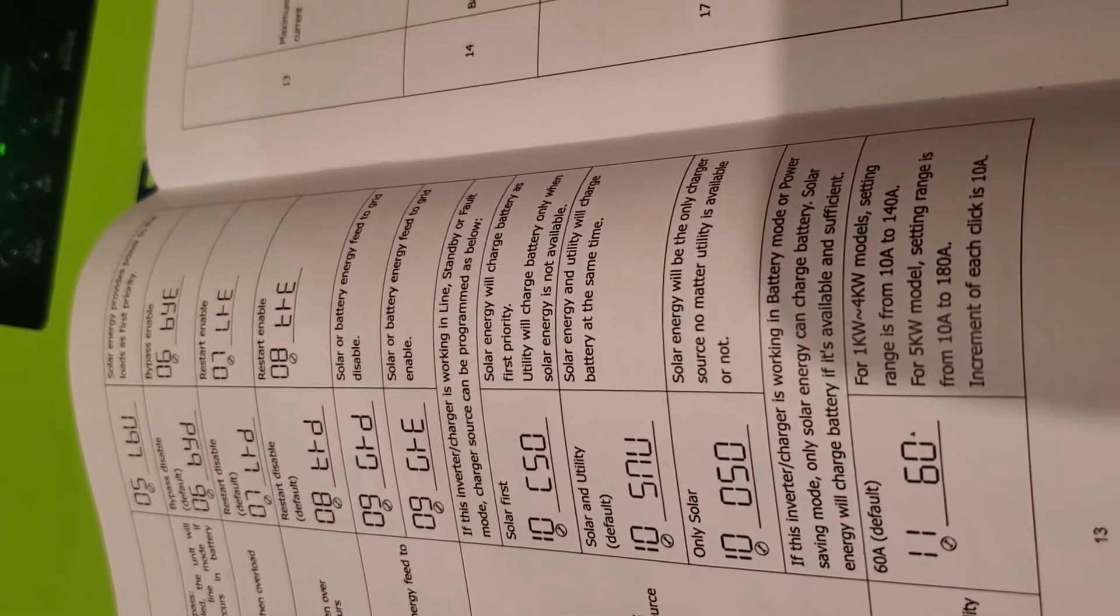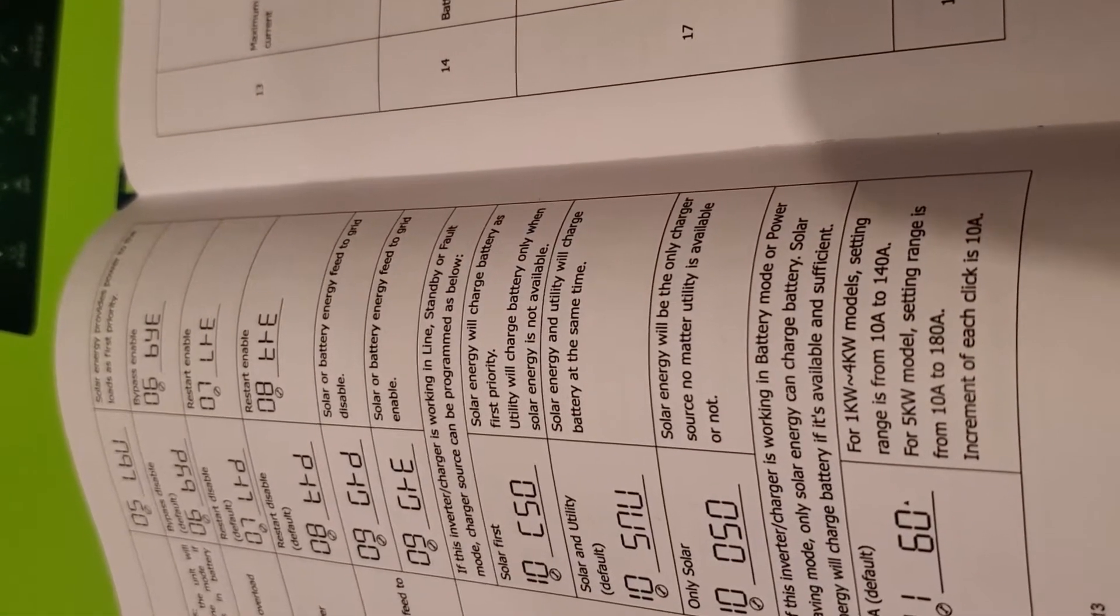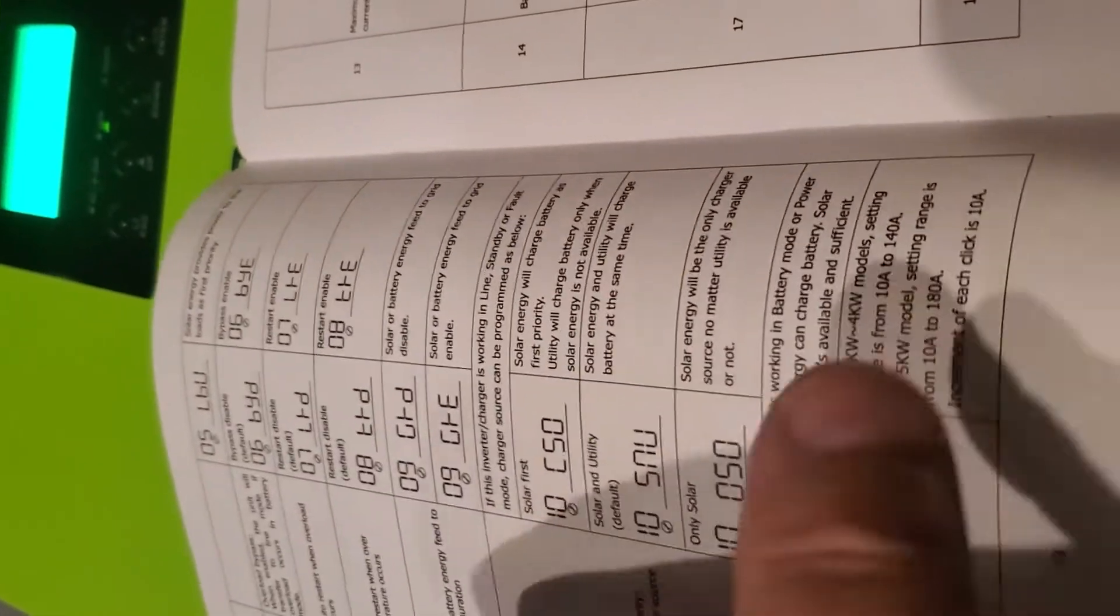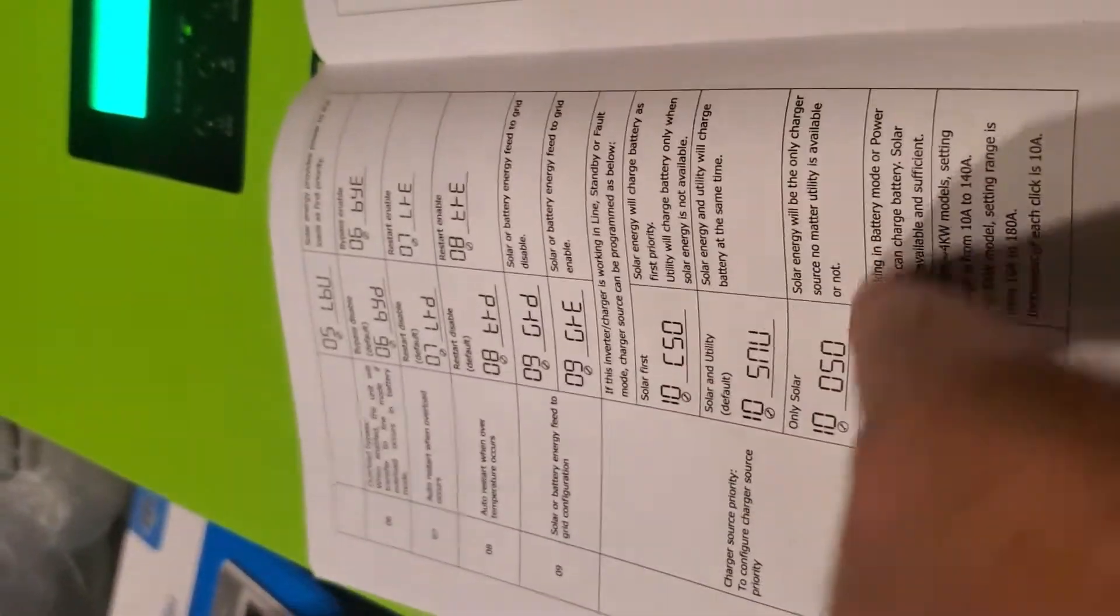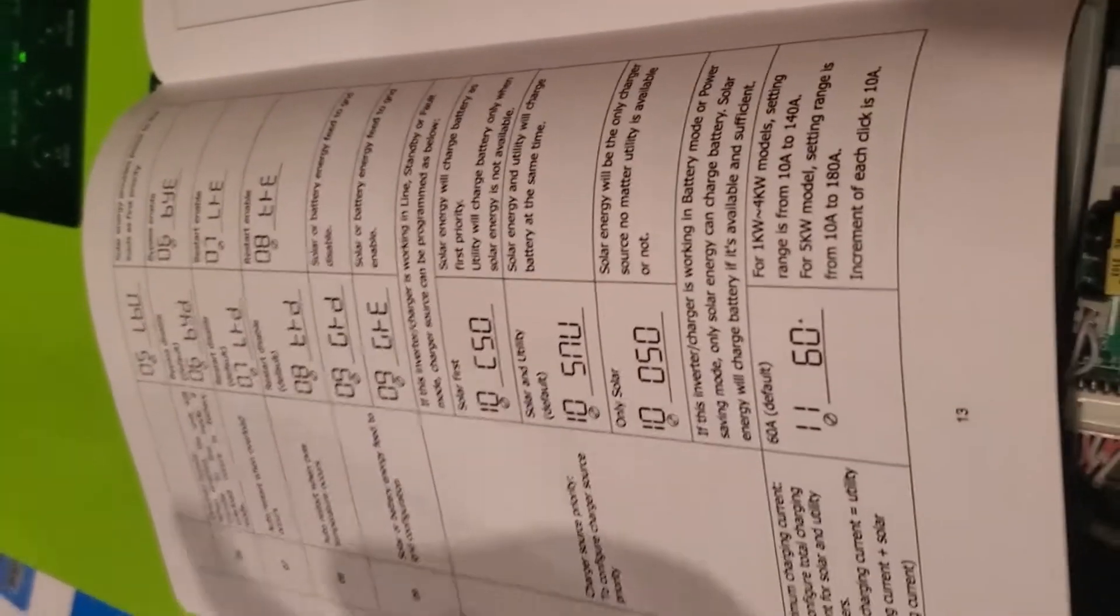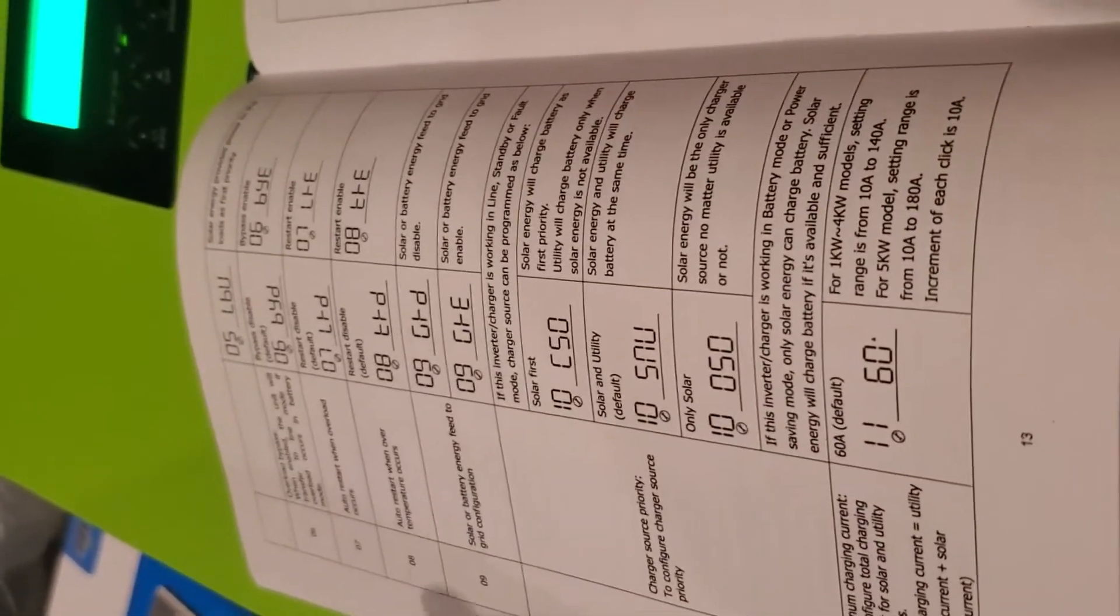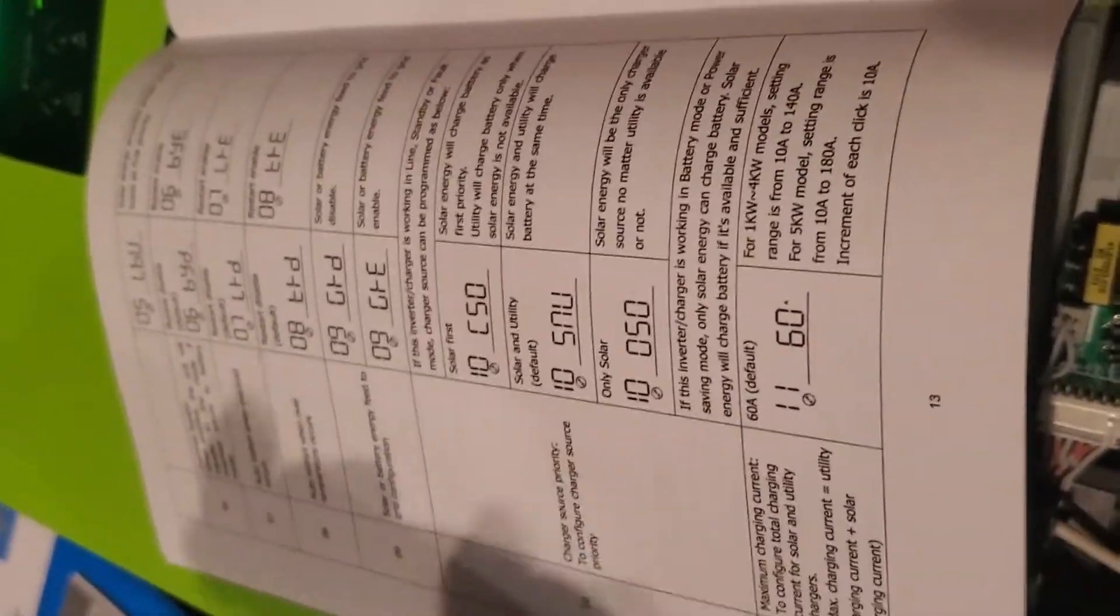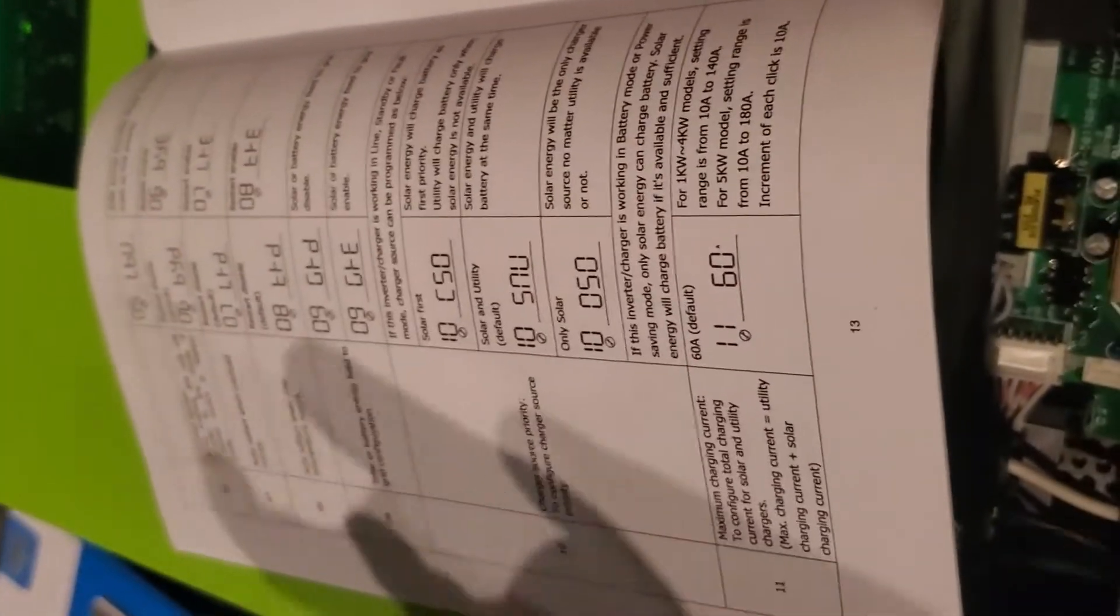Charger source priority. Solar first, solar and utility, or only solar. If this inverter charger is working in line standby or fault mode, charger source can be programmed as below. CSO is solar energy will charge the battery as first priority and the utility will charge the battery only when the solar is not available. The default is solar and utility. Solar energy and utility will charge the battery at the same time. You probably don't want this, you probably want the first one. I mean, why do we want to use the grid if we have solar? So only solar for me, it's only solar or that one. And what I would do is I would typically plug mine in at night and I would let it charge. Especially because I might run my batteries down kind of low during peak hours so that I can run the air conditioner and not have to pay those rates. So then I can just charge my batteries back up after seven o'clock and it won't cost me as much. So that's another good thing about that.